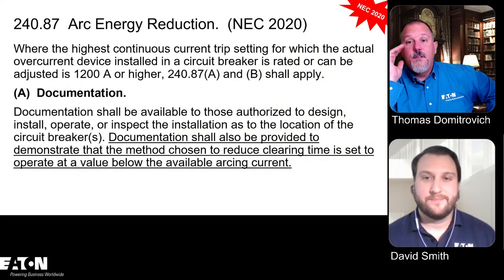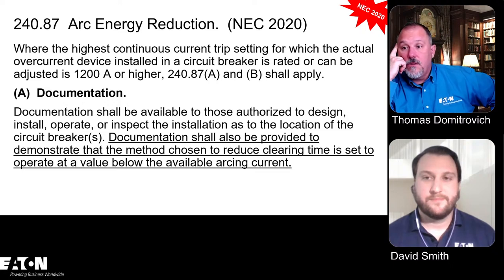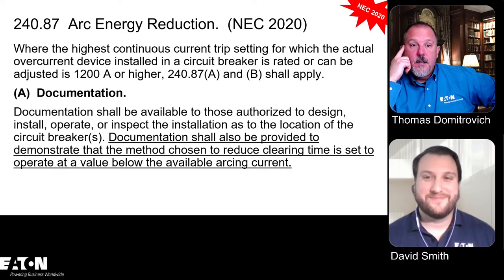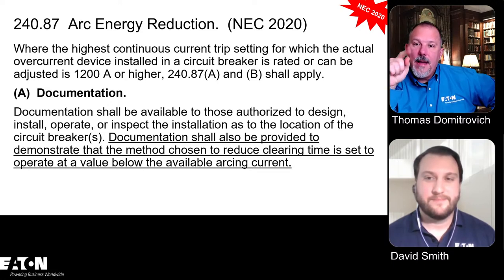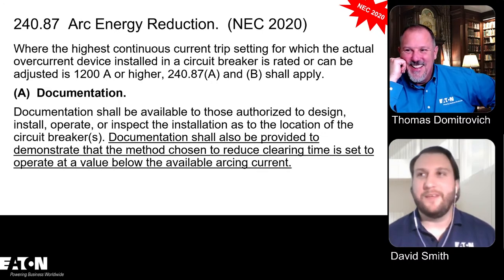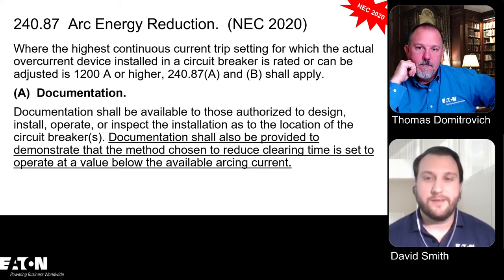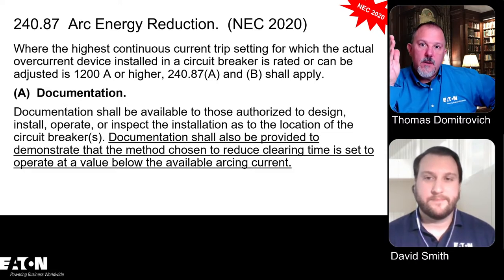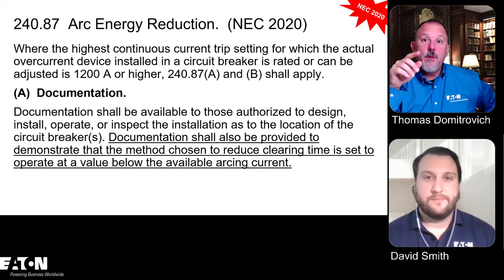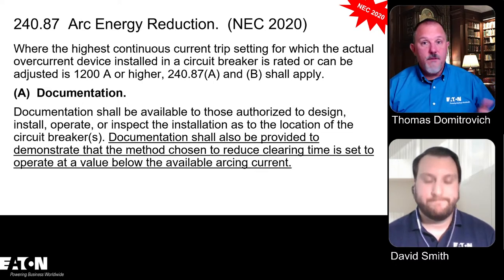Right off the bat, the focus in the 2020 cycle, David, was around arcing currents. We don't define arcing currents in the National Electrical Code. Now you pointed out maximum and minimum arcing current. Where do you get those terms from? You. No, just kidding. I think it's from IEEE, right? From 1584. Yeah. IEEE 1584 tells us that when you calculate arc, you calculate a minimum and a maximum arcing current for any value.